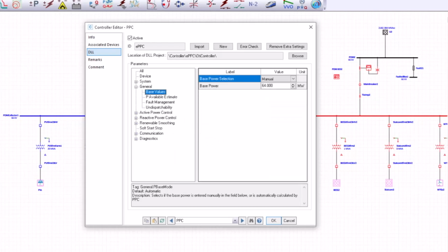The general settings concern more the general parameters of the plant. For example, the base value that we need to consider can be entered manually or calculated automatically by EPPC, how the PPC should behave in case there's a fault in the system, and if a device becomes undispatchable, how EPPC should handle that. Those kinds of settings are defined under the general settings.